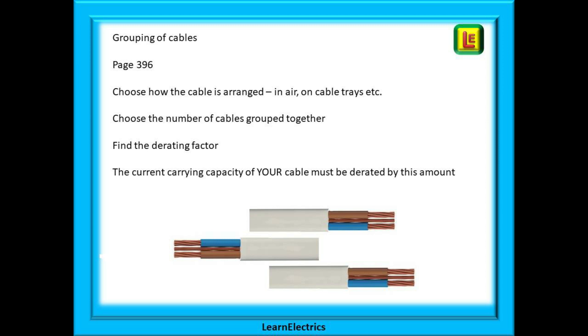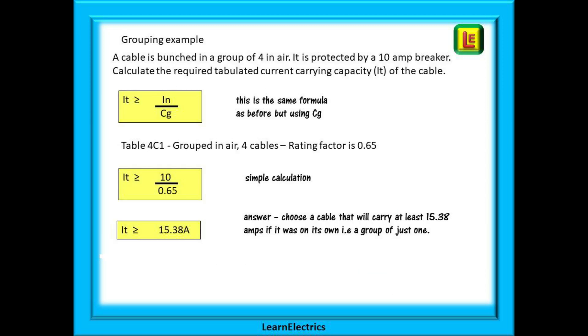Here on page 396 we must choose how the cable is arranged. In air, on cable trays etc. Then choose the number of cables that are grouped together including your own cable. Find the derating factor in the table and this tells us that the current carrying capacity of your cable must be derated by this amount. Try this question.